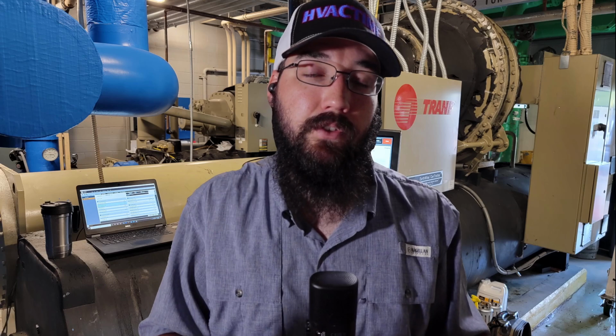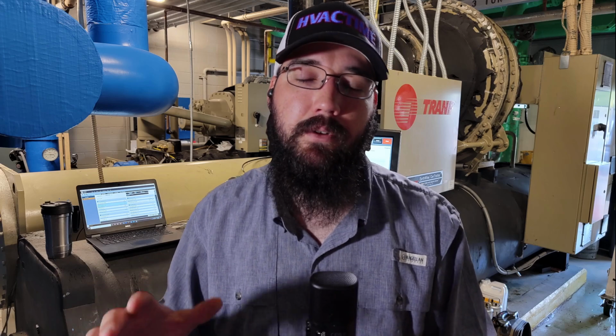These valves will typically go to full close, and when they go to full close, they will fully isolate if they're working properly. And if you don't force those valves open whenever you do your recovery, there are times where it can trap refrigerant in there, and you get in and start working on stuff thinking you're good, and either the valve suddenly loses seal and opens a little bit, or you go to take something apart on the still pressurized part of the system thinking it wasn't pressurized, and you get hurt or something very negative happens. So these are things we have to be careful with on EXVs, but they have this capability, and so our ability to control flow is far more expansive. We can technically go from 0 to 100%, where with a TXV we could only do say 30 to 100%, give or take, right?